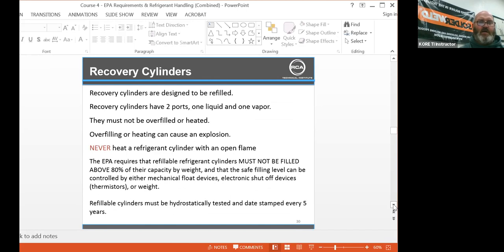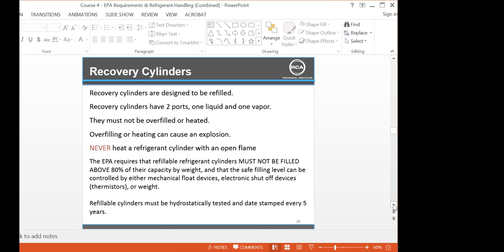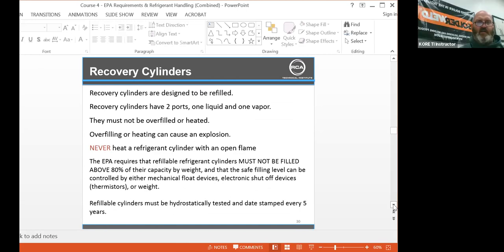Overfilling or heating can cause an explosion. Never heat a refrigerant cylinder with an open flame. The EPA requires that refillable refrigerant cylinders must not be filled above 80% of their capacity by weight, and that the safe filling level can be controlled by either mechanical float devices, electronic shutoff devices, thermistors, or weight. Refillable cylinders must be hydrostatically tested and date stamped every 5 years.